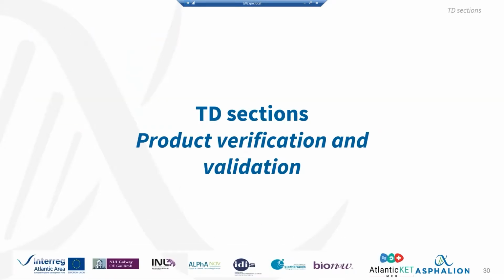Okay. This is just a reminder for what we said before. When there's a residual risk, it should be included in the instructions for use. Okay, if you manage to reduce as much as possible all your risks, but there's still residual risk that the patient or the user should be aware of, you still have to include that in the instructions for use. Okay, this is what we were making reference to before.